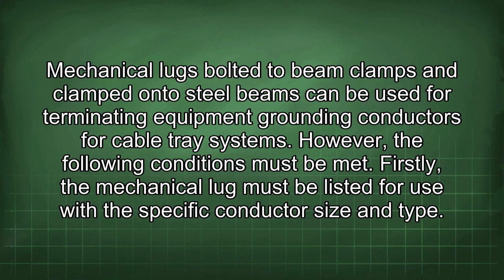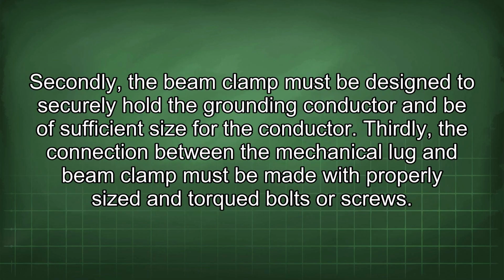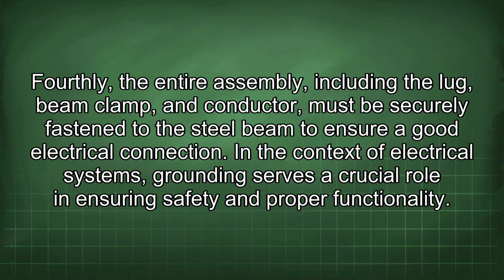Mechanical lugs bolted to beam clamps and clamped onto steel beams can be used for terminating equipment grounding conductors for cable tray systems. However, the following conditions must be met. Firstly, the mechanical lug must be listed for use with a specific conductor size and type. Secondly, the beam clamp must be designed to securely hold the grounding conductor and be of sufficient size for the conductor. Thirdly, the connection between the mechanical lug and beam clamp must be made with properly sized and torqued bolts or screws. Fourthly, the entire assembly, including the lug, beam clamp, and conductor, must be securely fastened to the steel beam to ensure a good electrical connection.